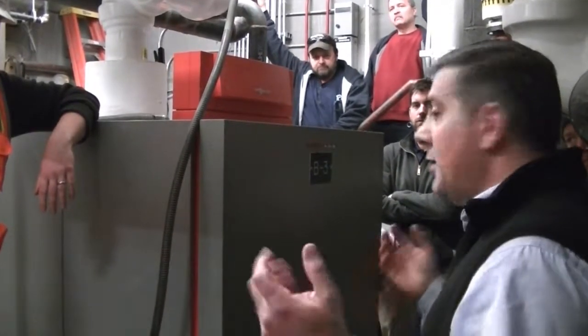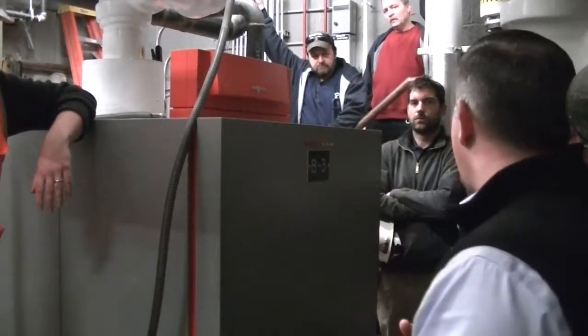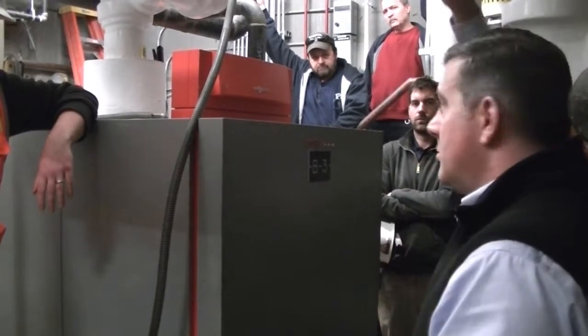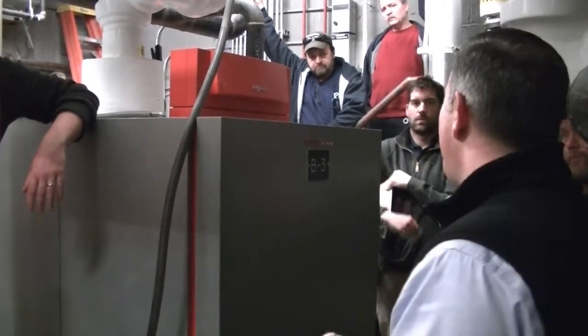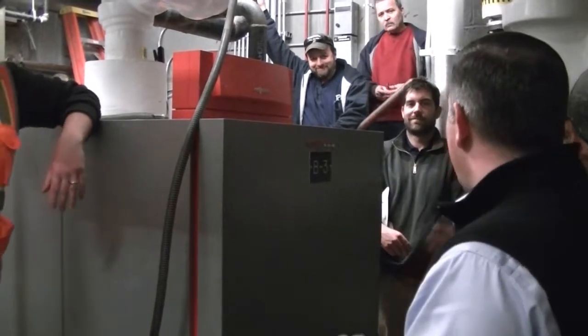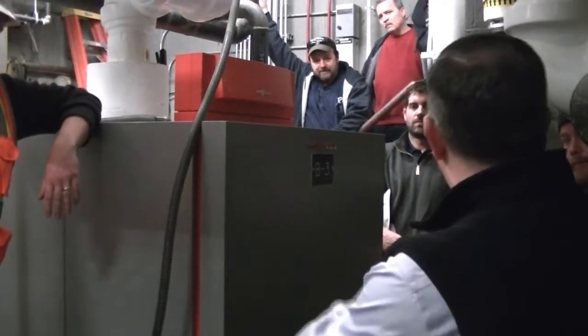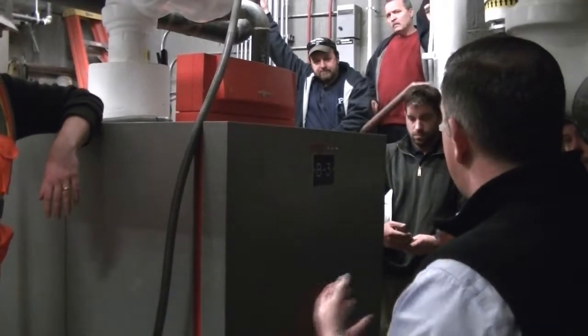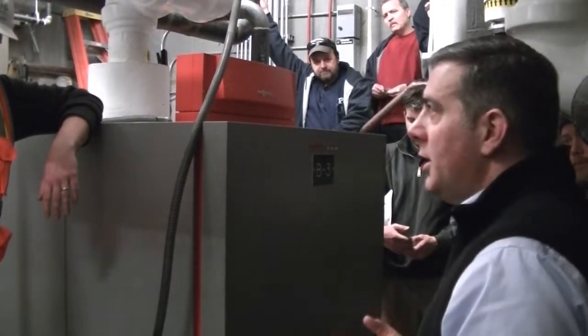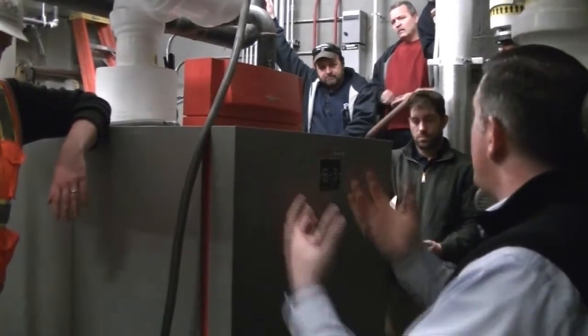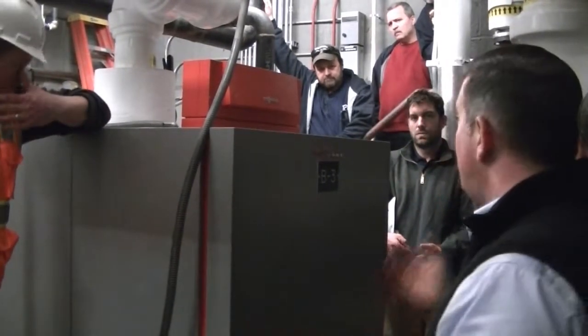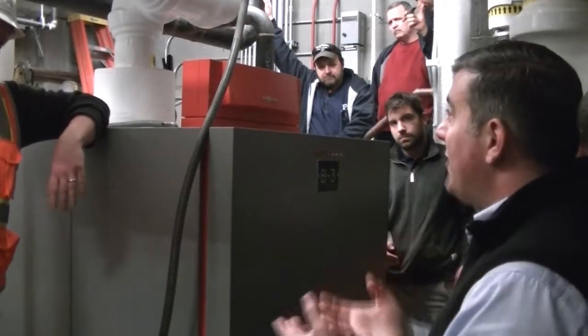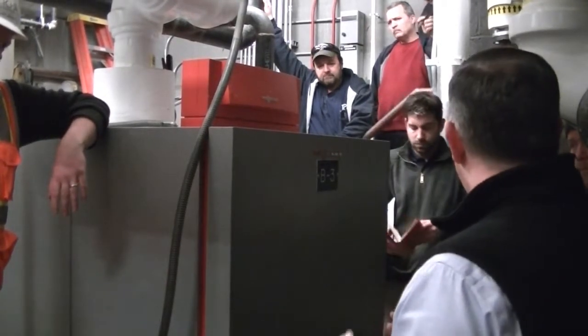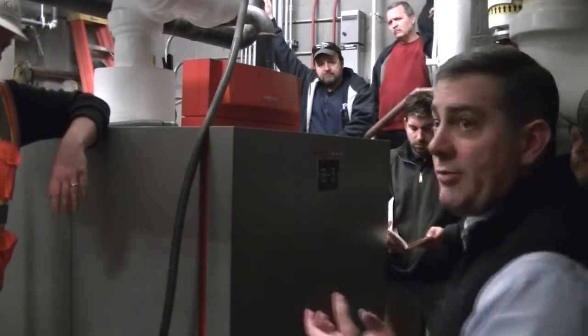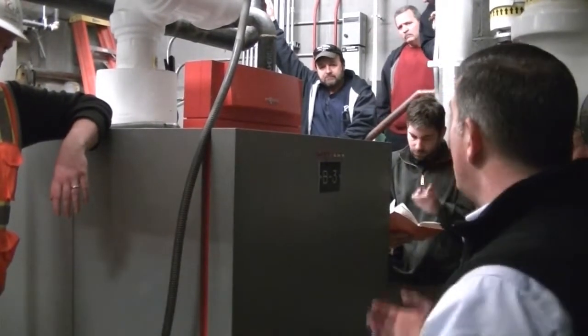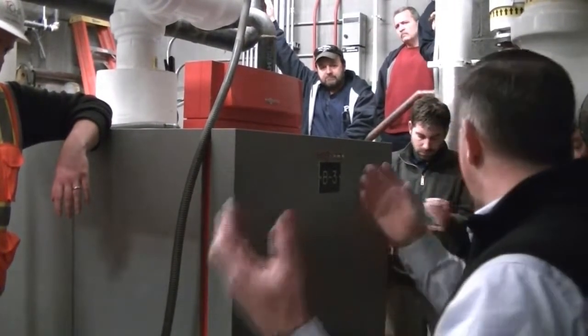Now, how do we cool off the flue gas temperatures going up the stack? Anybody want to guess? You didn't know there was going to be a test, did you? As the return water comes back from the system, it's given up all its heat to the baseboard and the radiators in the building, so it comes back to the boilers a little bit cooler. That cooler water temperature is what actually cools off the flue gas. So ideally, you want water temperatures coming back to the boilers lower than 130 degrees, because that's the only way you're going to cool the flue gas temperatures below 130 degrees. So the cooler the water temperatures are in the system, the higher your efficiency is going to be.